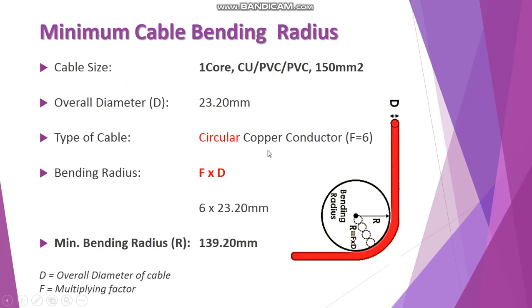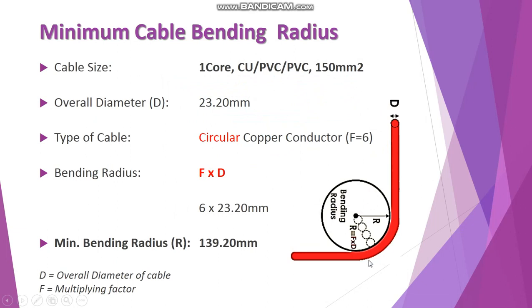Since we are using a circular copper conductor, the multiplying factor is 6. So: R = 6 × 23.20 = 139.20 mm. This means we cannot bend our cable less than 139.20 mm. If we do, the cable may get damaged — especially the insulation, and in certain conditions the conductor strands inside the cable may also get damaged, which is not good for the cable in the long run. So be very careful when installing cables on site.